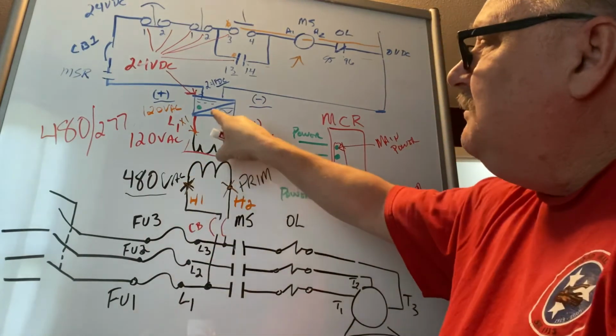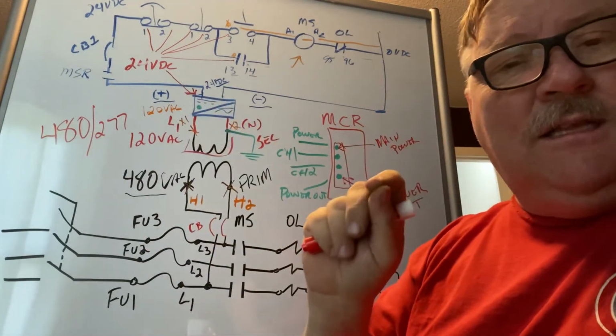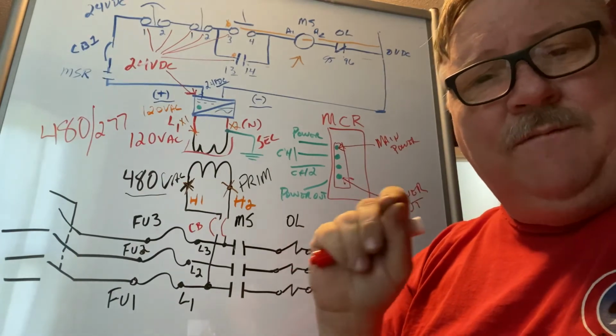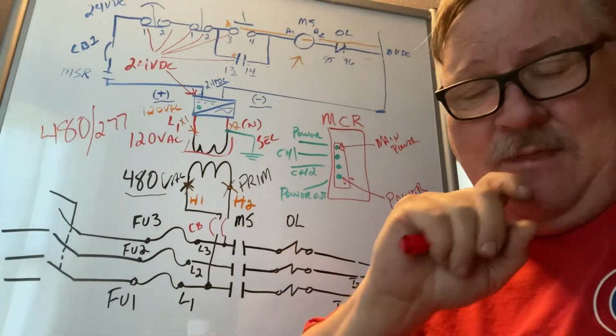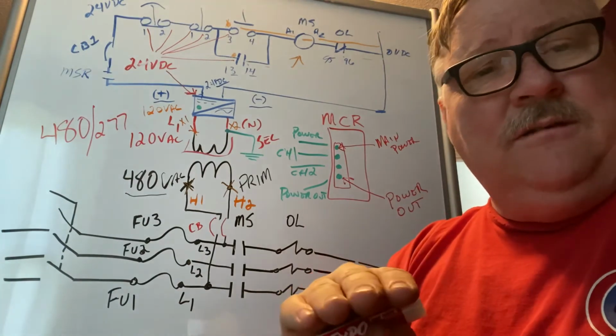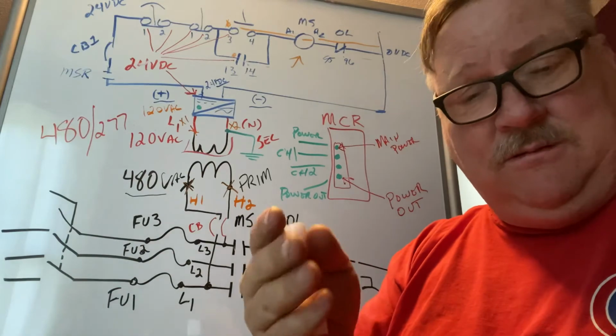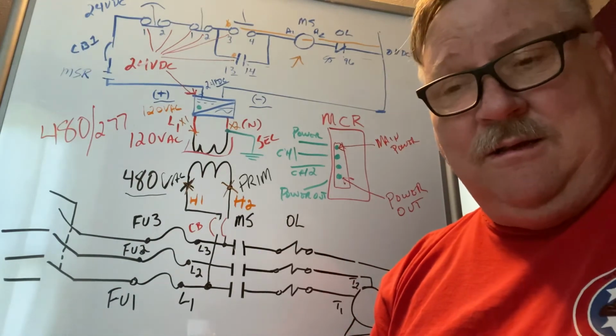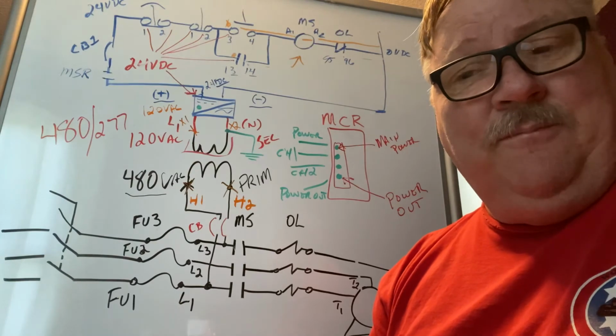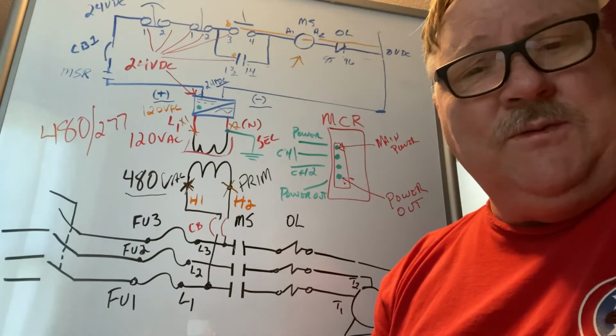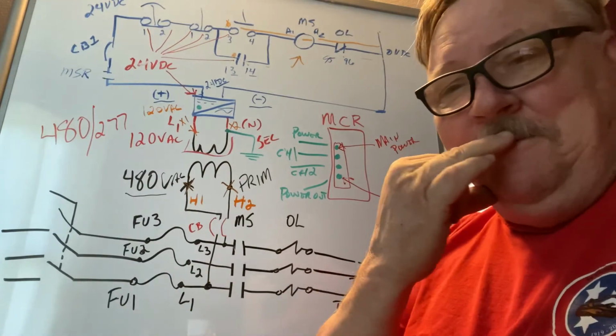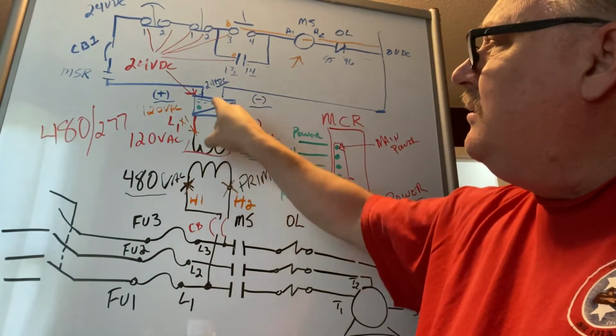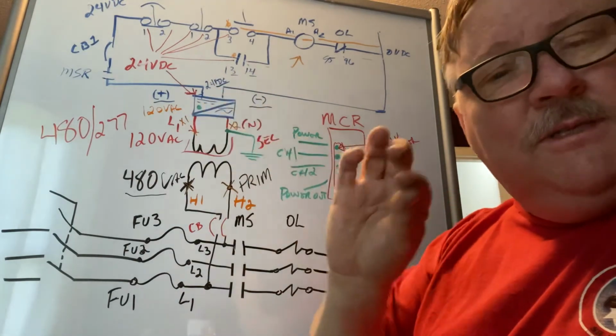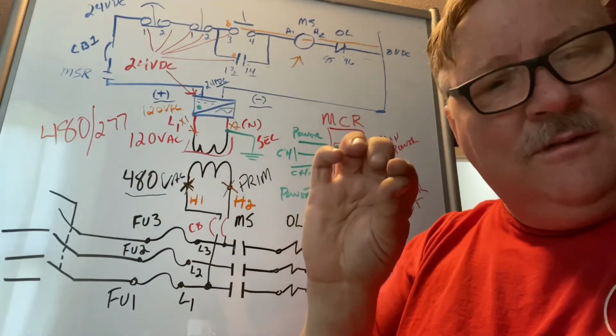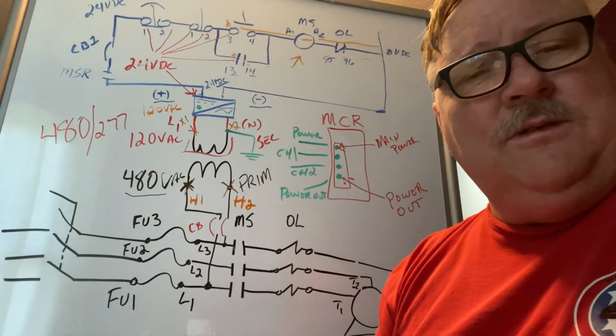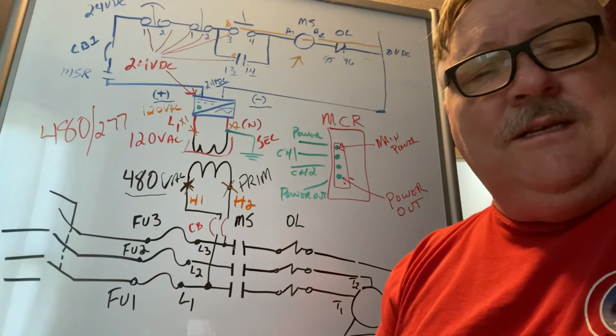Okay. Power supplies typically have a green status light. They don't all, but most of them will. If that green status light is not on, that is not necessarily completely indicative that the power is gone, because those things, don't ever trust a status light. Those things will fool you. They'll stay on when nothing's happening, and they'll go off when everything's working. So they're not completely trustworthy. But check your power. If you got 120 going in, you should have 24 volts going out. Sometimes you have a little potentiometer. Let's say you're getting 22. You can go in there and tweak that to bring the voltage up to 24, where you need it to be. Okay.